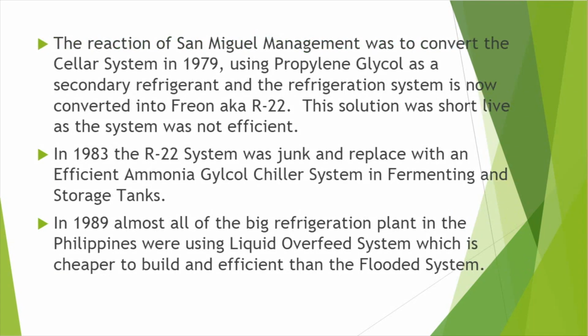The reaction of San Miguel management was to convert the cellar in 1979 using propylene glycol as secondary refrigerant, and the refrigeration system was converted into Freon or R22. The solution was short-lived, as the system was not efficient. In 1983, the R22 system was junked and replaced with the efficient ammonia glycol chiller system in its fermenter and storage tank. In 1989, almost all of the big refrigeration plants in the Philippines were using liquid overfeed, which is cheaper to build and more efficient than the flooded system.